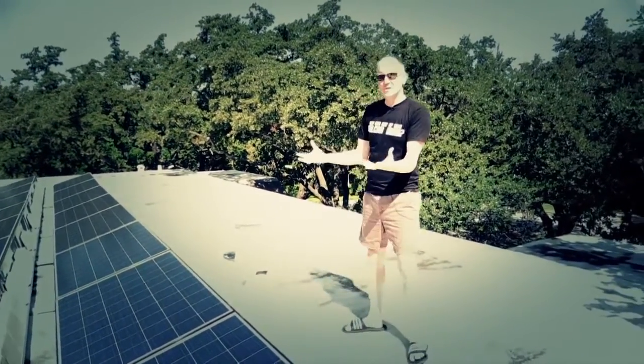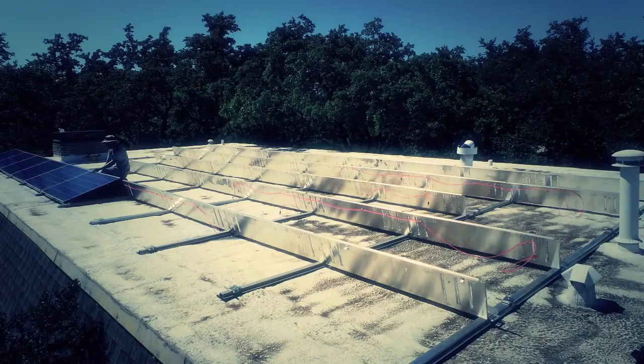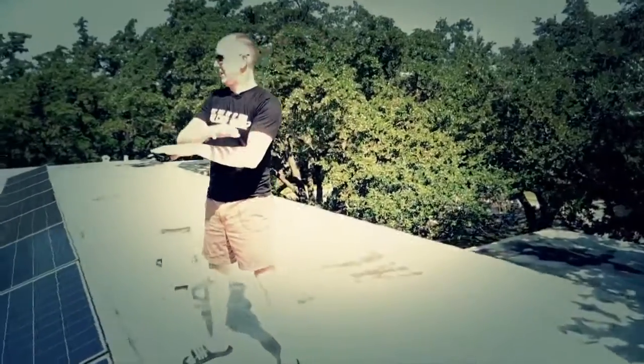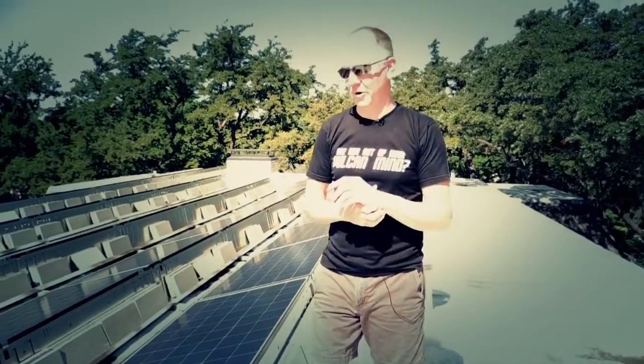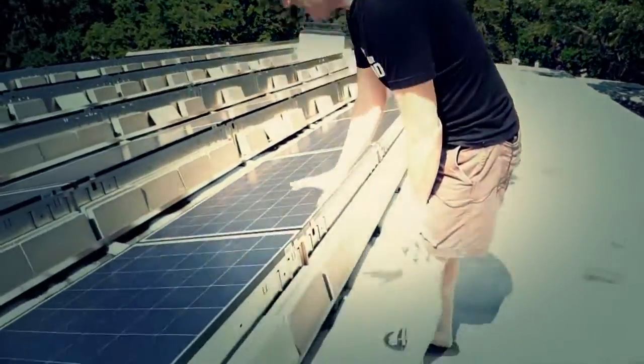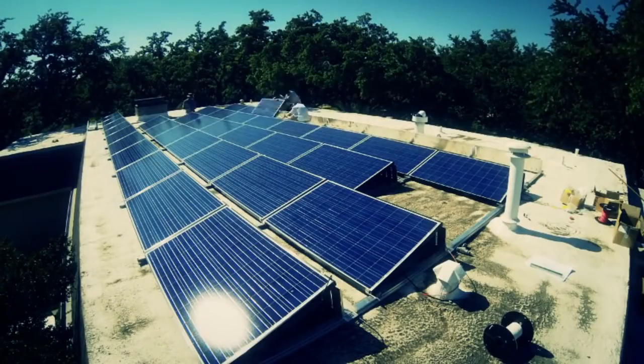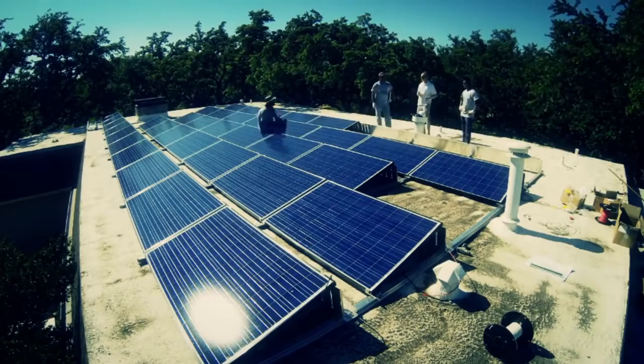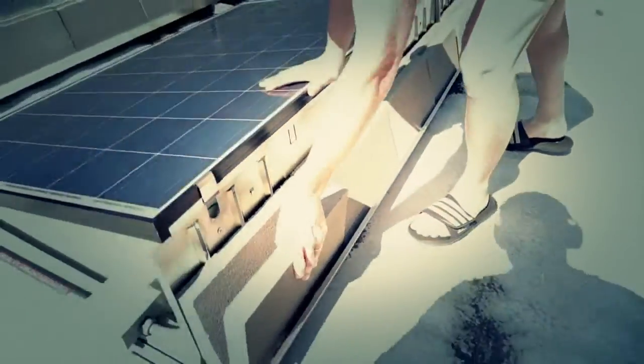We had to keep the solar panels a little bit away from the chimney. Now let's talk about how the system goes together. This is what's called a ballasted system — it is not bolted to the roof. The last thing we wanted was hundreds of screws in our roof, which on a flat roof especially could cause problems down the road. So instead, this system uses a series of rubber pads underneath the railing. They built the whole railing first, then dropped the solar panels on, and finally put ordinary little concrete paver stones on top for weight.